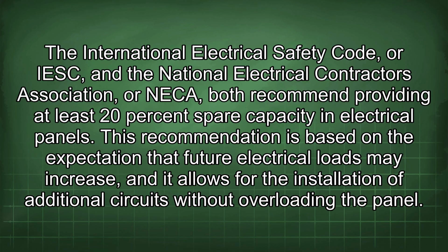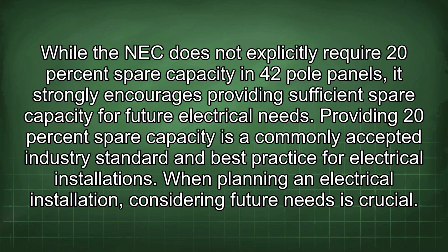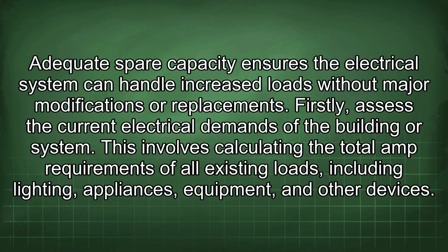This recommendation is based on the expectation that future electrical loads may increase, and it allows for the installation of additional circuits without overloading the panel. While the NEC does not explicitly require 20% spare capacity in 42-pole panels, it strongly encourages providing sufficient spare capacity for future electrical needs. Providing 20% spare capacity is a commonly accepted industry standard and best practice for electrical installations. When planning an electrical installation, considering future needs is crucial. Adequate spare capacity ensures the electrical system can handle increased loads without major modifications or replacements.